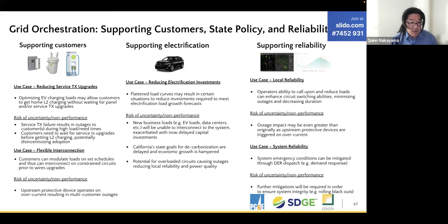Now, some of the risk and uncertainty is that if we still overload the circuit because of non-performance, then an upstream device will operate and now 2,000 customers are out of power. That becomes a pretty big problem for us. So those are some of the risks of uncertainty and non-performance around flexible interconnection.